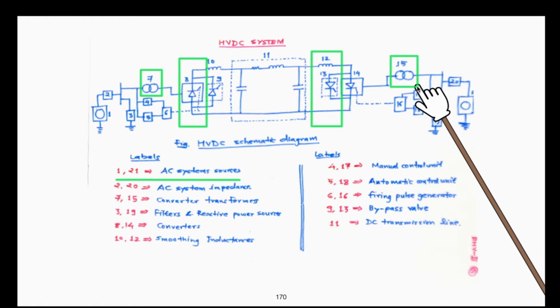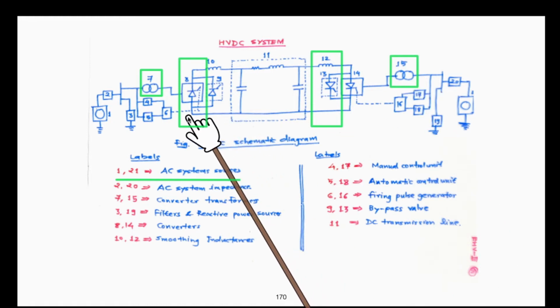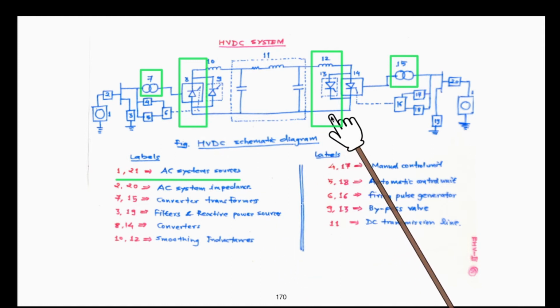This is due to the fact that the converter and inverter work with 12 pulse operation, right? For 12 pulse operation, you require a 30-degree phase shift between the line voltages. So you require 6 different line voltages displaced by 30 degrees with respect to each other, so that 12 pulse operation can be obtained.